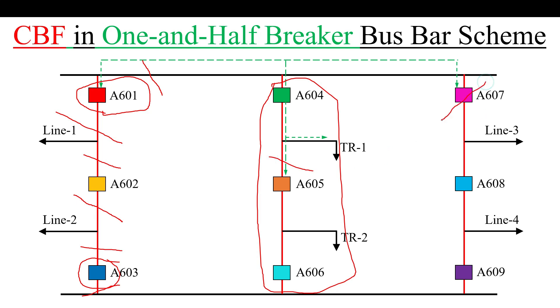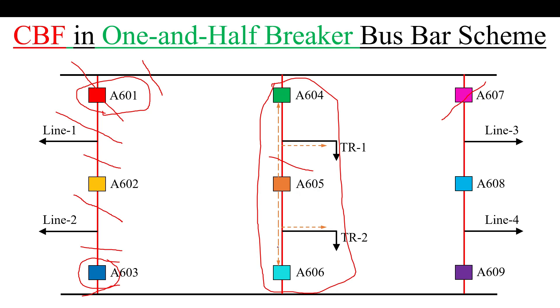Once these associated breakers operate, the transformer section becomes isolated and no supply remains. For A605 failure specifically, tripping from its CBF relay is extended to A604 and A606. There is no need to trip TR1 or TR2, but if it were a transmission line, tripping would be extended to it — that is why the arrows are shown.